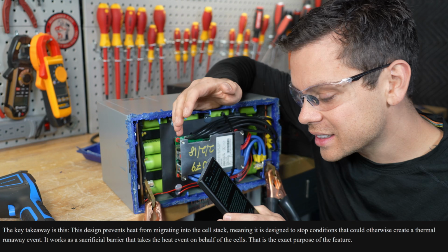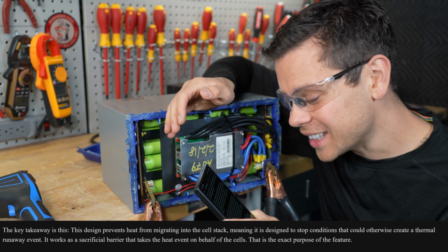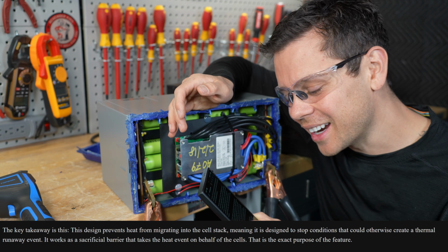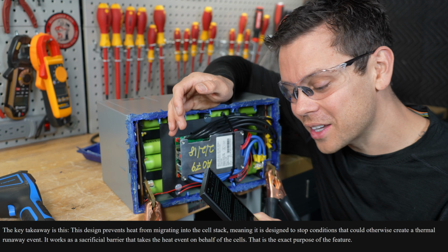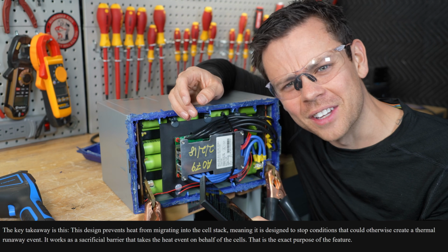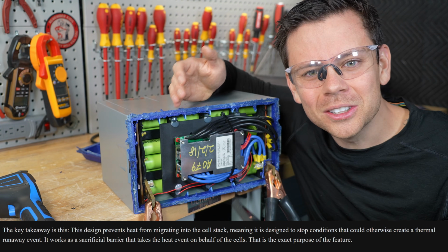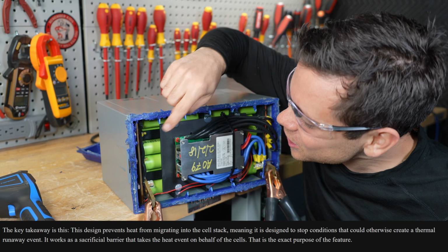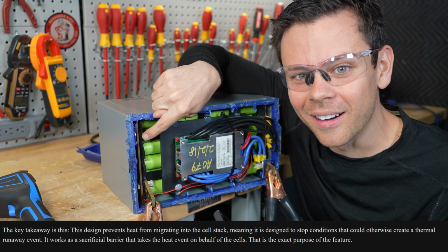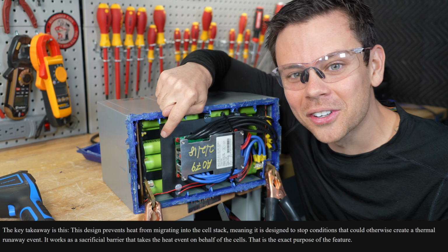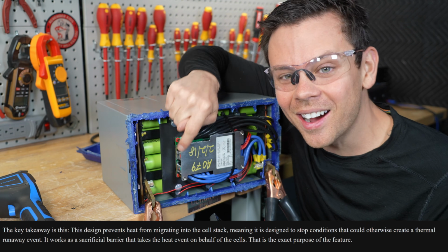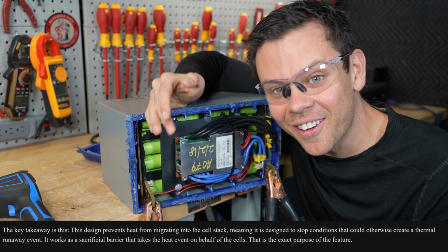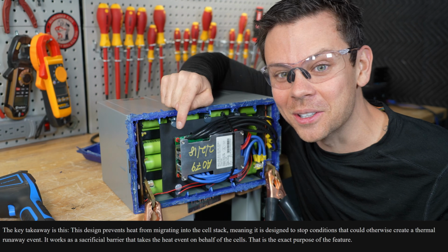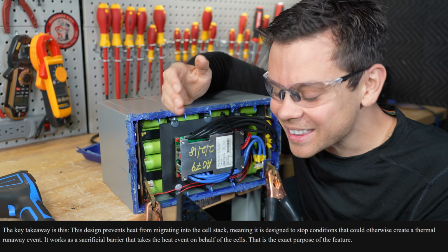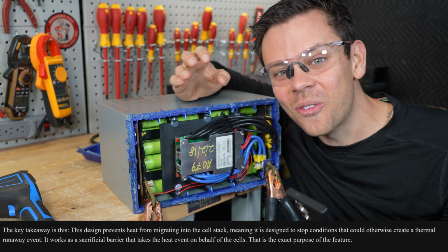This design prevents heat from migrating into the cell stack, meaning it is designed to stop conditions that could otherwise create a thermal runaway event. That is absolutely and utterly false. Look at the color of this bus bar. Everything on here is overheating these cells, and it's not disconnecting. It is still arcing. This is 100% an issue. To say that this is a safety feature is wild to me.